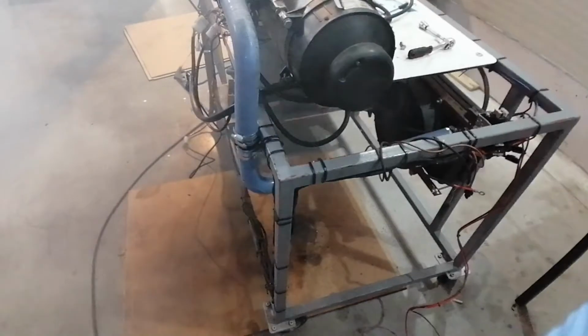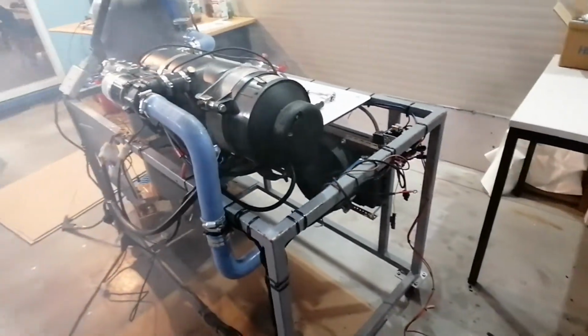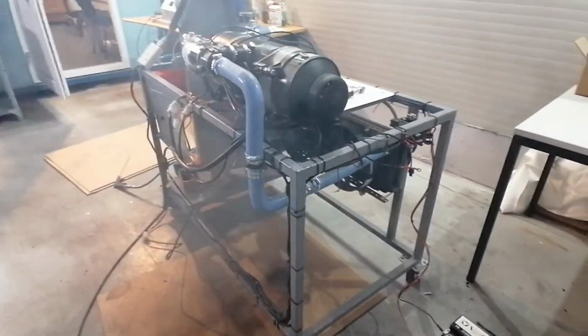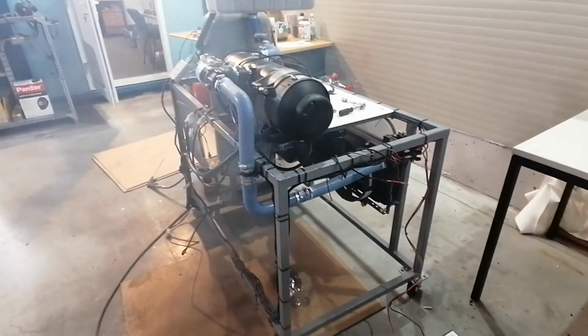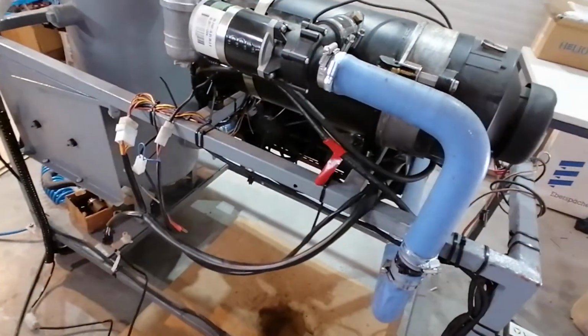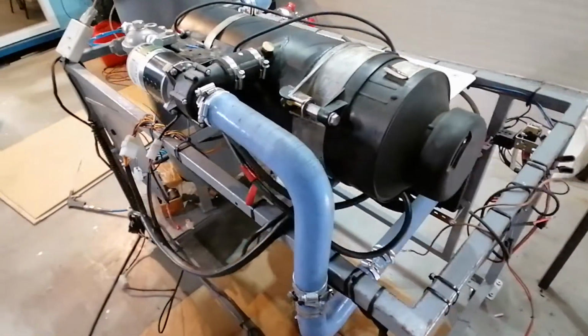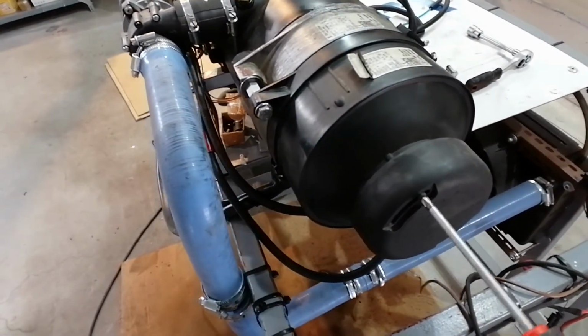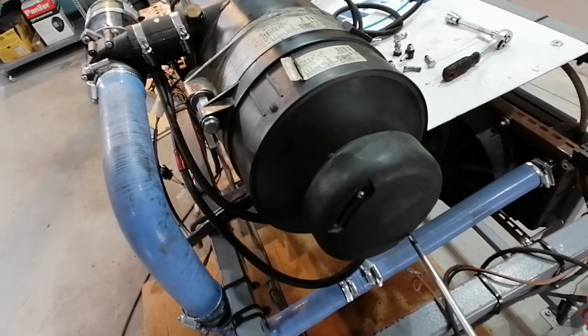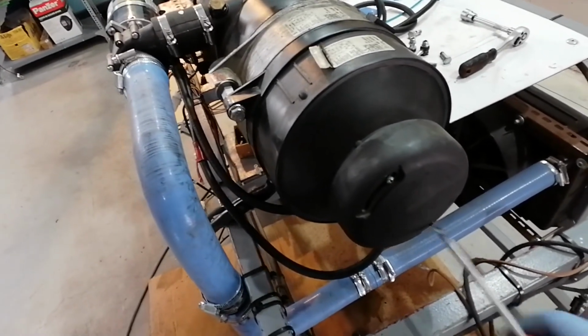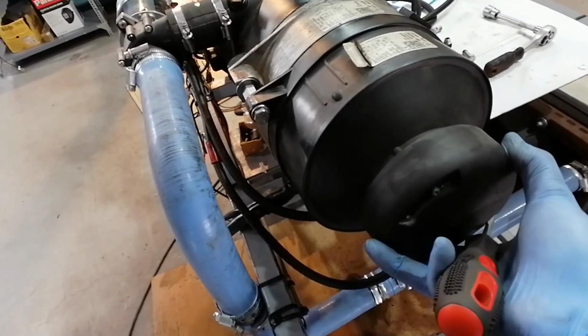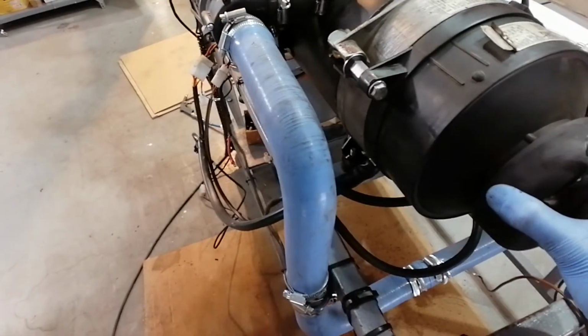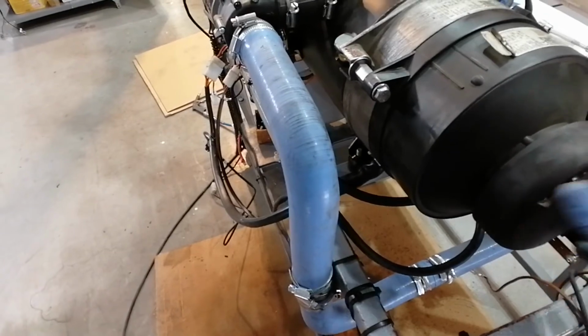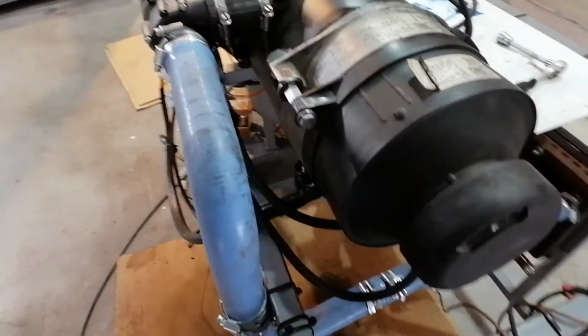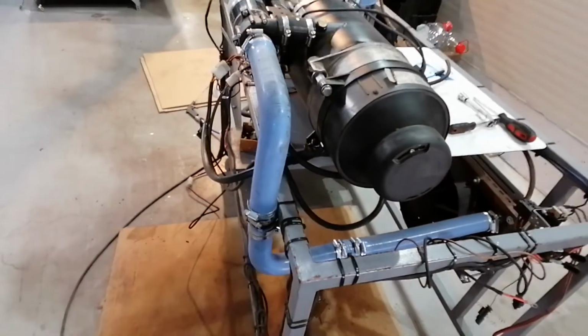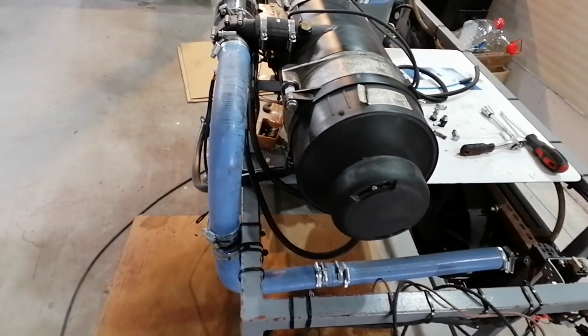It's clear that we will have to make some CO2 adjustments. I will just open the door for now and leave the smoke to clear out a little bit. It's pretty clear to me that the unit is working with too high CO2 settings, so for now I will open these two setting screws and reduce the CO2 level a little bit, just to give the unit the chance to clear out. I'll put it here in the middle, and after the unit gets to operating temperature, we'll use a CO2 meter to set this exactly to the specification.